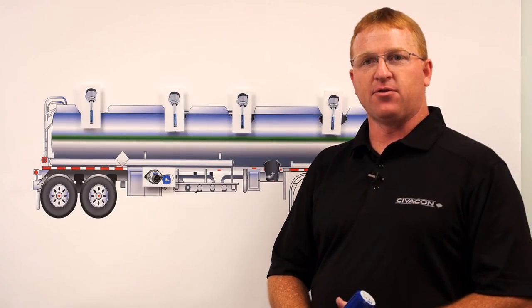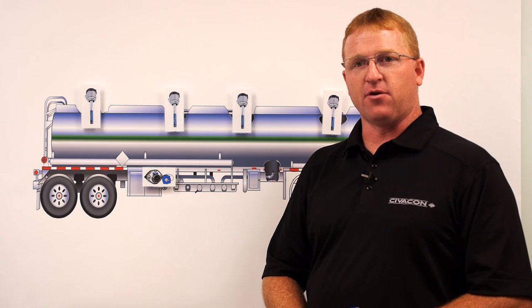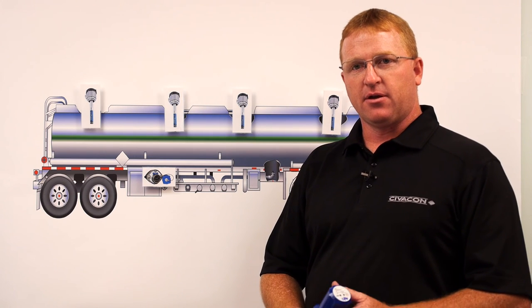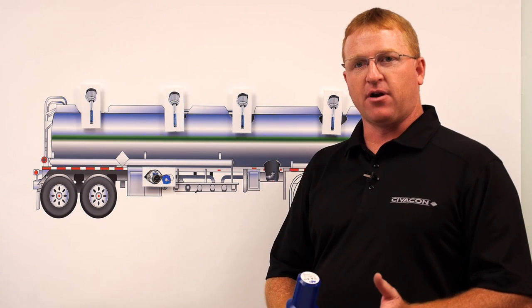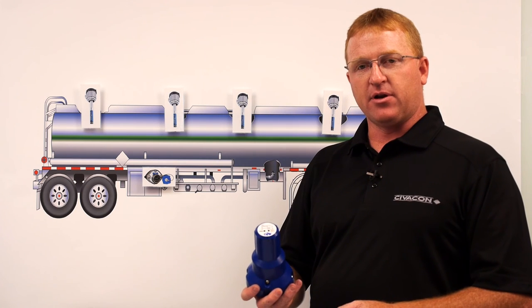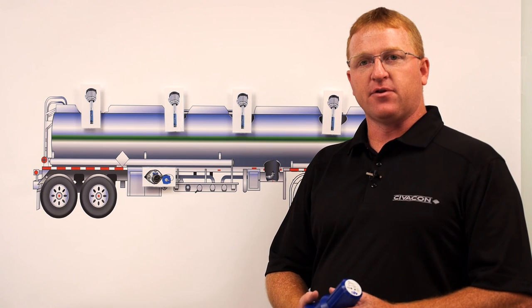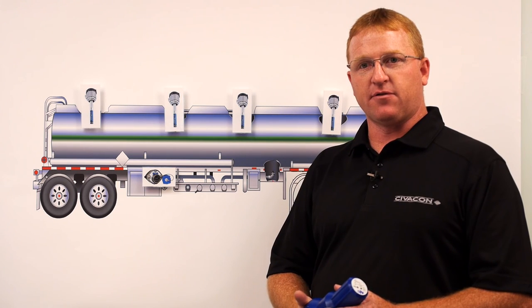That completes the troubleshooting of two issues commonly found on a 5-wire overfill system: wiring problems and a defective probe. A third problem commonly found is in the grounding circuit, which can be determined if your tester shows a fault in the ground system. We have an extensive video on this at civacon.com that explains how to troubleshoot the ground circuit. This concludes our troubleshooting of the 5-wire overfill systems and the three most commonly found issues. If more support is needed, please refer to civacon.com or contact our 1-800-TECH-LINE.